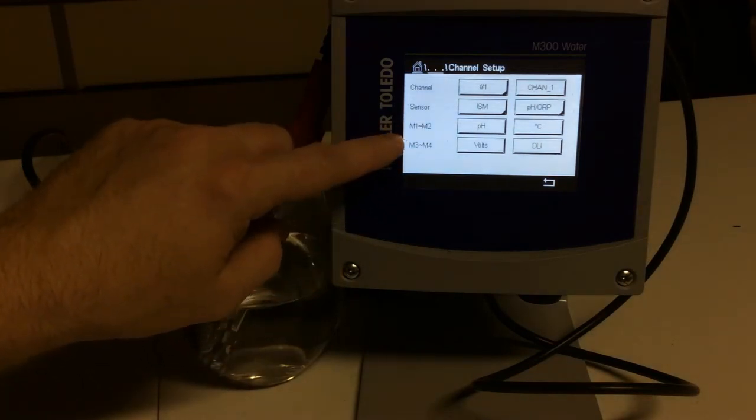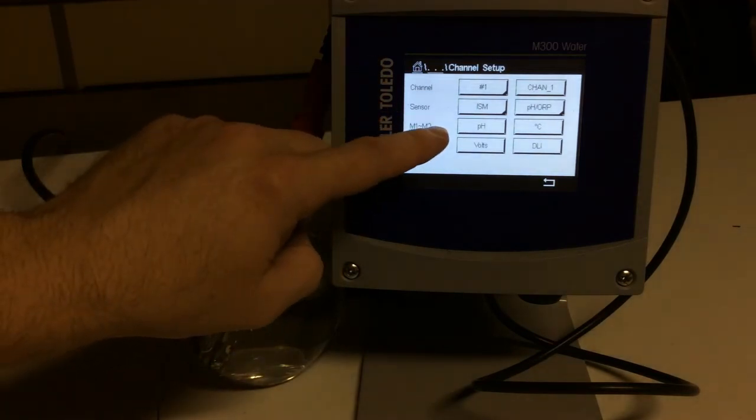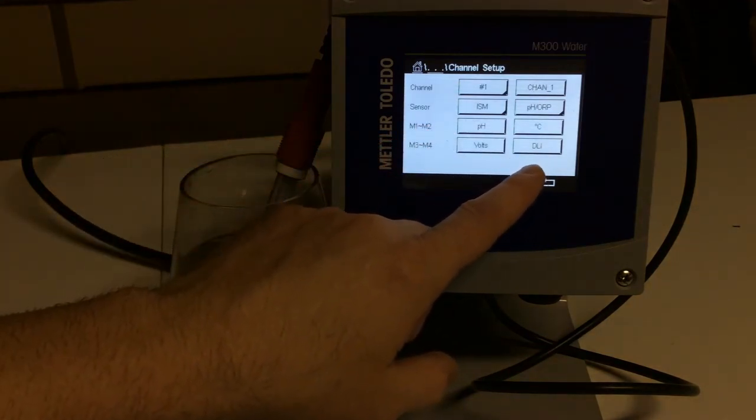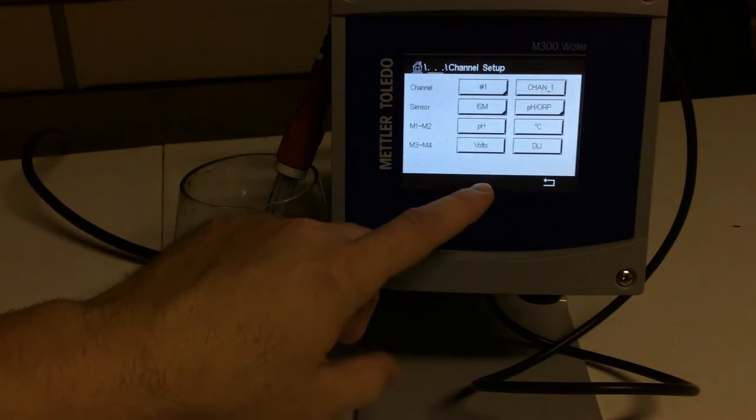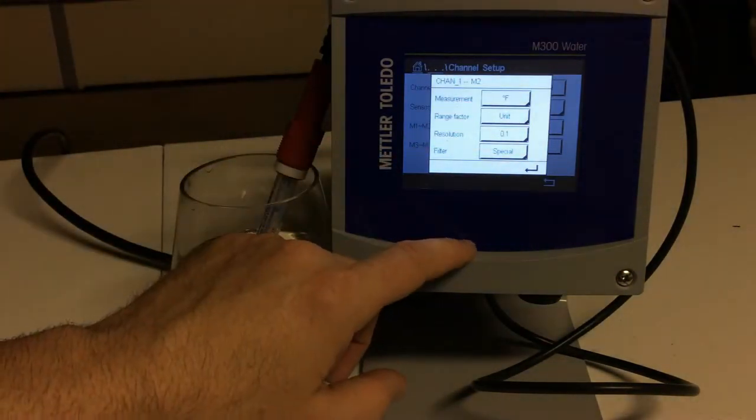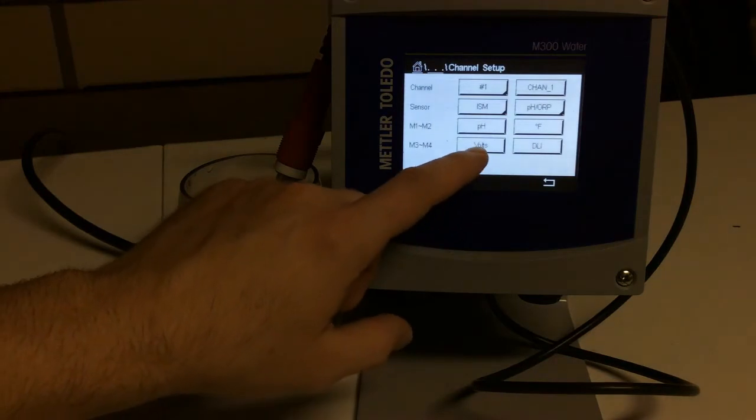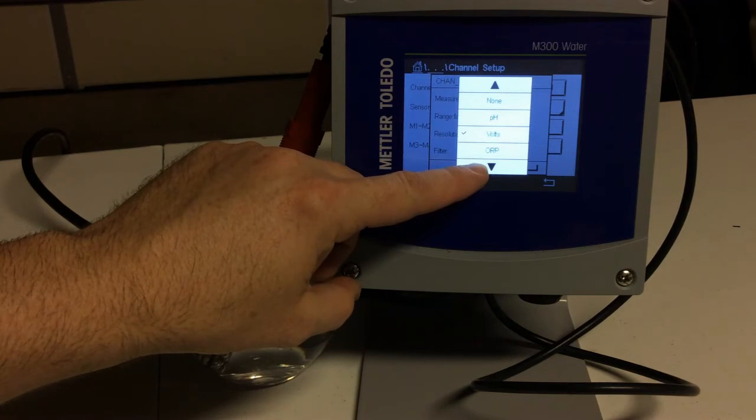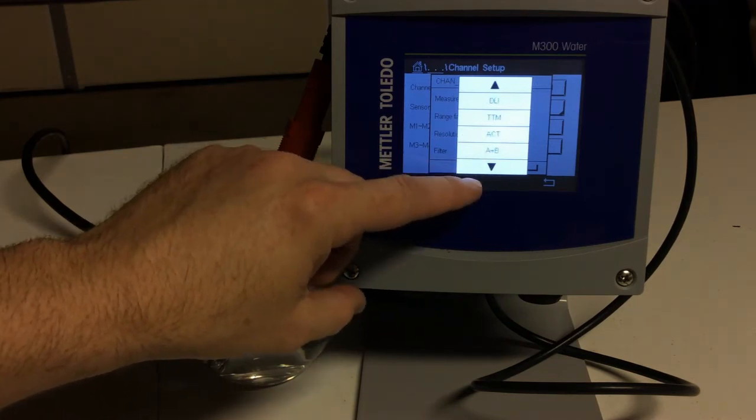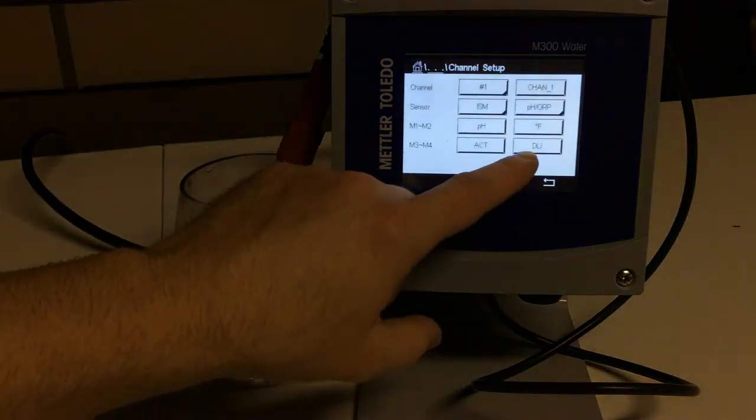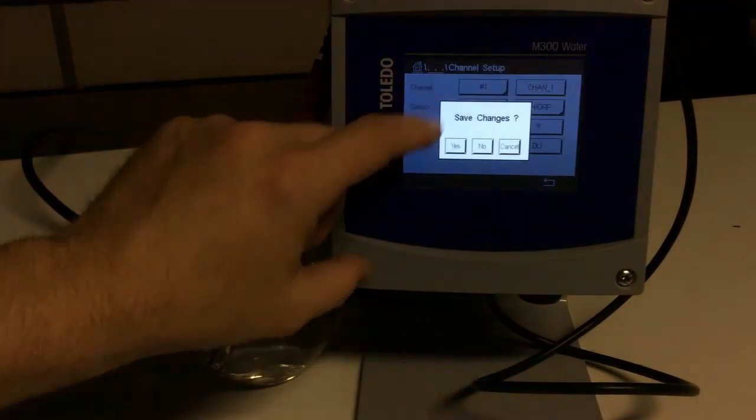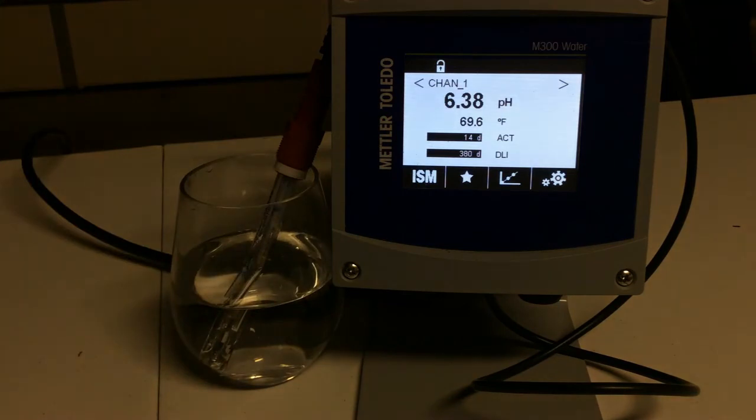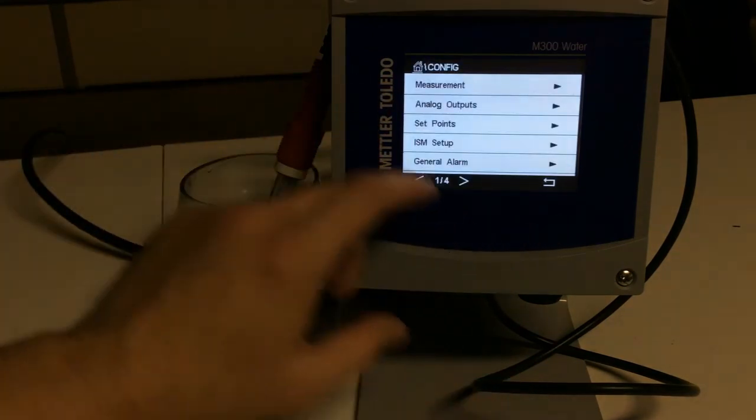So M1 through M4 is the different measurements that we see on our home screen. So we were seeing pH, we see our temperature in Celsius, we see our volts, and we also see our DLI, Dynamic Lifetime Indicator. So let's say you want to see your temperature in Fahrenheit instead of Celsius, there's also a lot of other different things that you could see, and we don't care about our volts. We've already got pH, I don't want my ORP, there's my Celsius, I want to see my calibration timer, and then I got my Dynamic Lifetime Indicator, and that's how I want to see it. I can sit here and go home, I want to save those changes, and now there's my view. So I've got my pH, my temperature in Fahrenheit, calibration timer, Dynamic Lifetime Indicator. Again, you can customize those however you want.